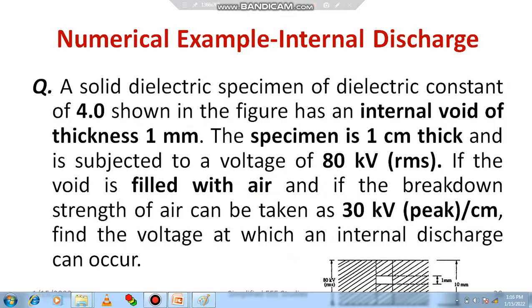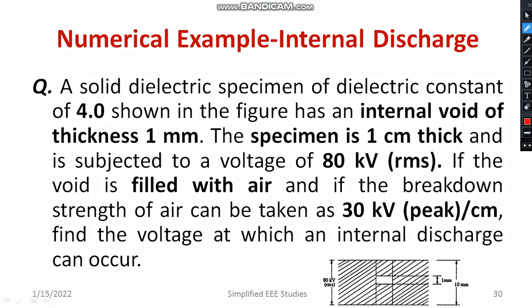Before that, let us read out the numerical example. Whenever you are going for insulation design or design of insulating material, you need to consider internal discharge. A solid dielectric specimen of dielectric constant 4, as shown in the figure — a rectangular piece of solid dielectric material — has a dielectric constant equal to 4. The internal void has a thickness of 1 mm, and the specimen is 10 mm thick, subjected to a voltage of 80 kV RMS.